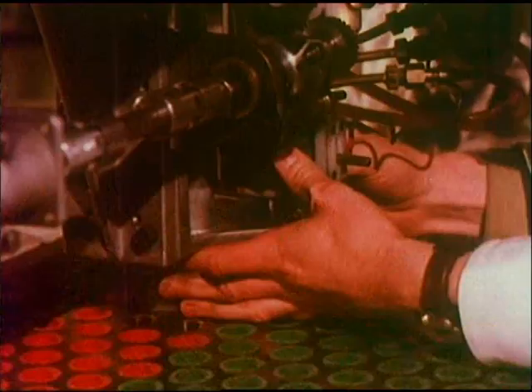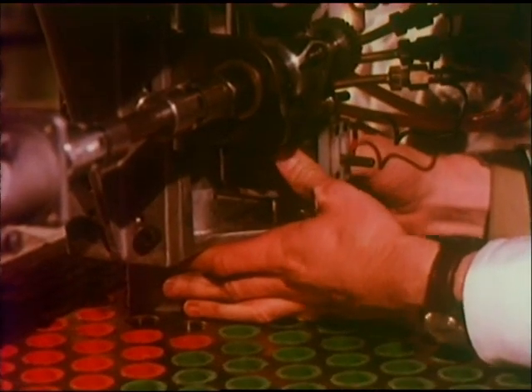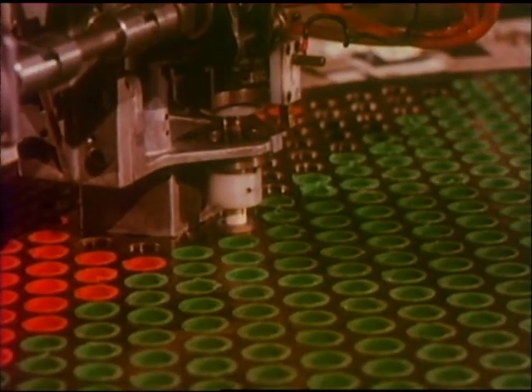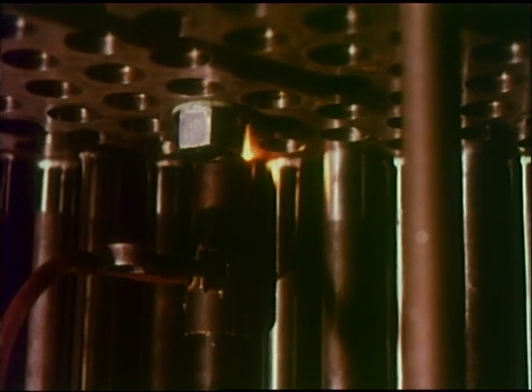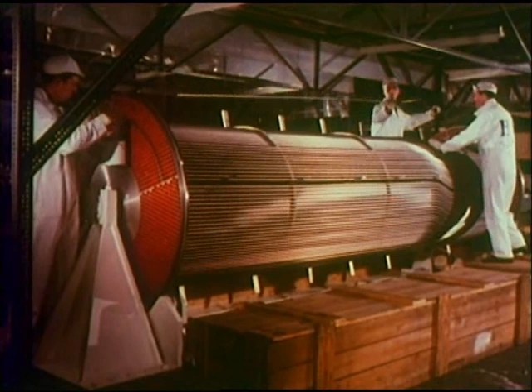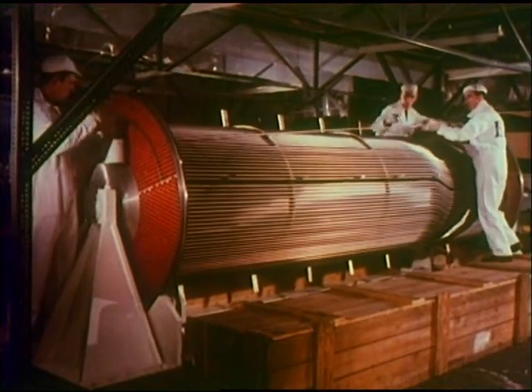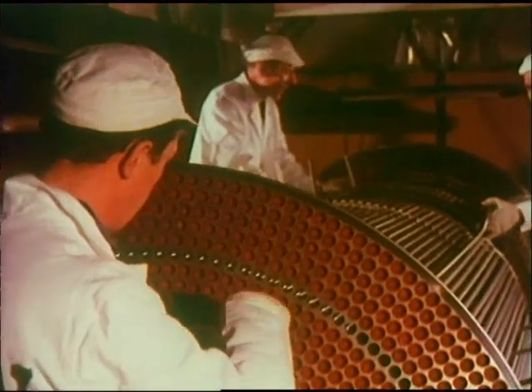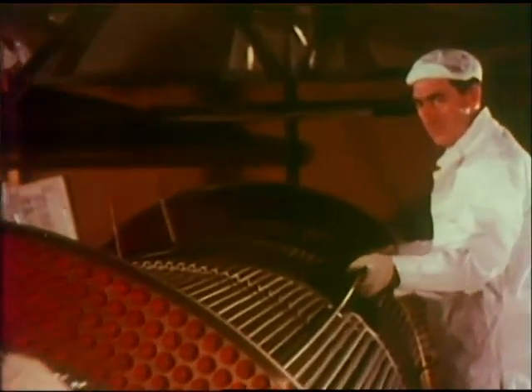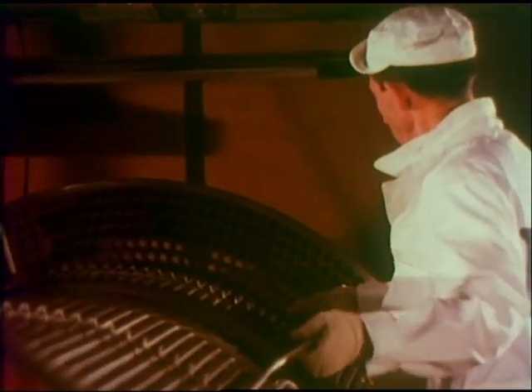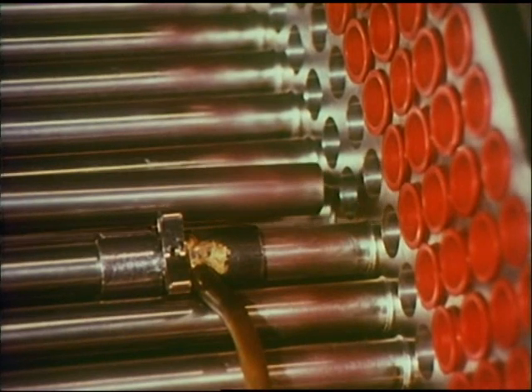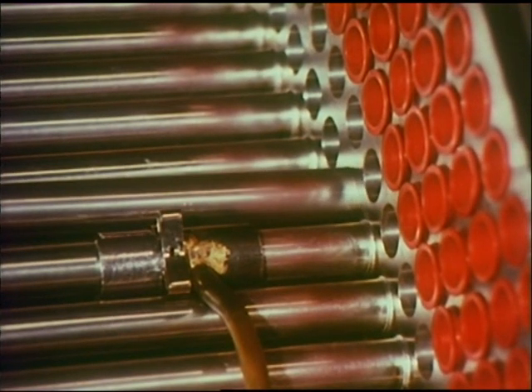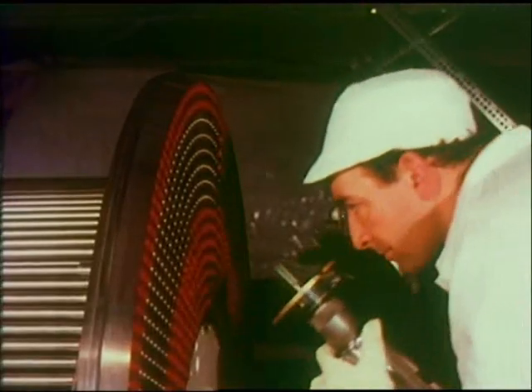The evaporators, reheaters and superheaters required for generating steam are basically similar. In all of them, bundles of tubes like these form the vital sodium-steam interface. The intermediate heat exchangers, in contrast, were works assembled with their tubes horizontal. These are of the counterflow shell and tube type, the primary sodium entering the tubes at 585 degrees centigrade. Argon-arc automatic welding was used throughout.